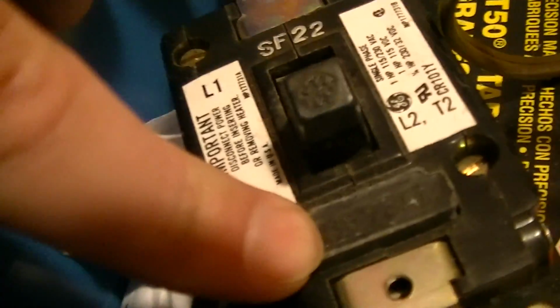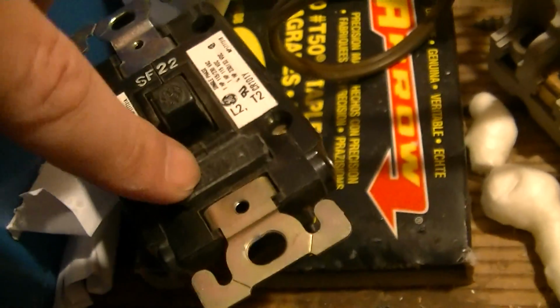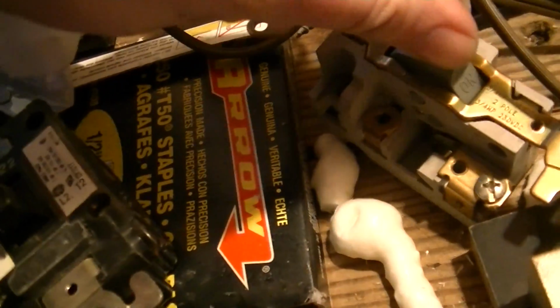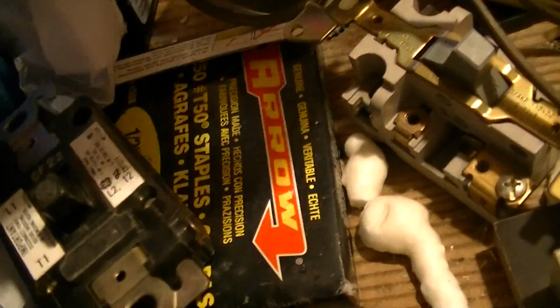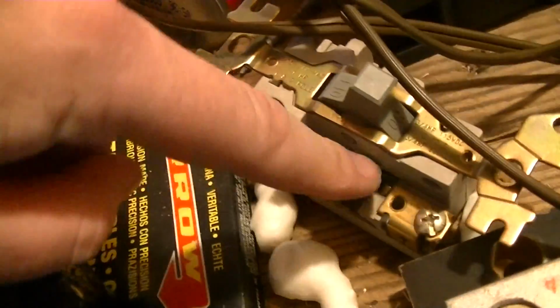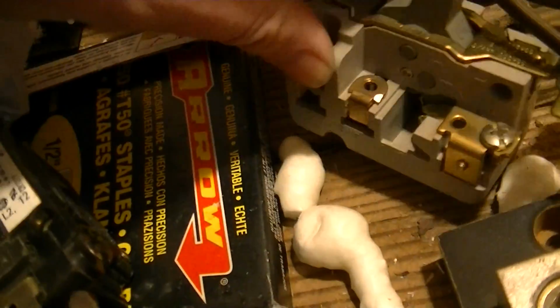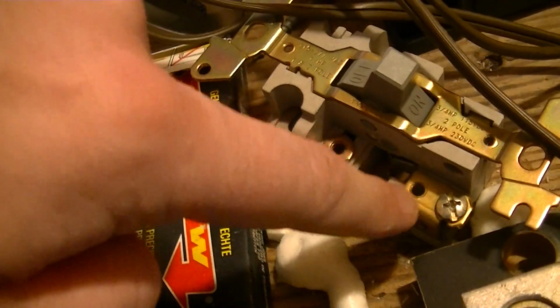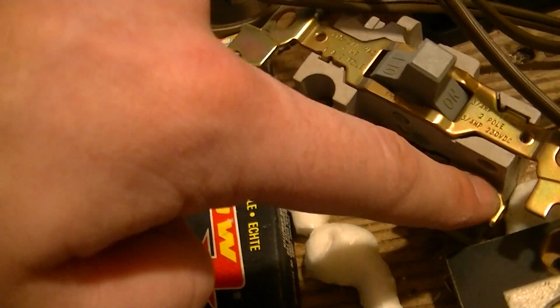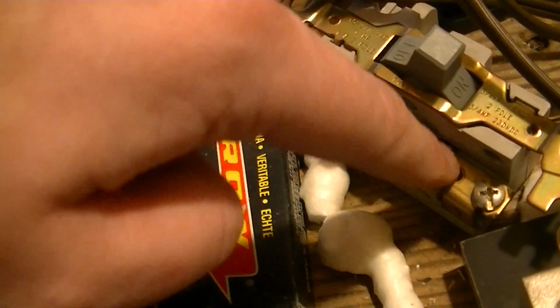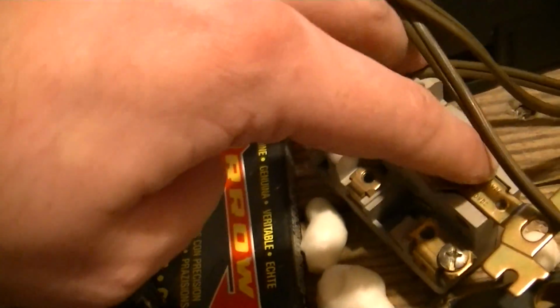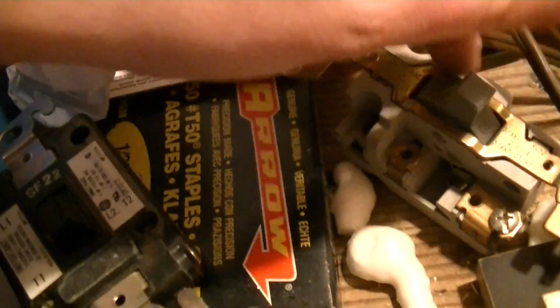Like for example this one, it's 8.73 amperes. It's very common for them to be oddball current ratings because those current ratings correspond to the typical overloads of a given size motor at a given potential. Or this one, this Siemens one, where the heater just screws onto those two things. Or they can take the screw, move it over, or just replace these with a wire link or a fuse or something, and turn it into a DC rated wall switch, which is the entire reason why I had this guy. That was also General Electric.